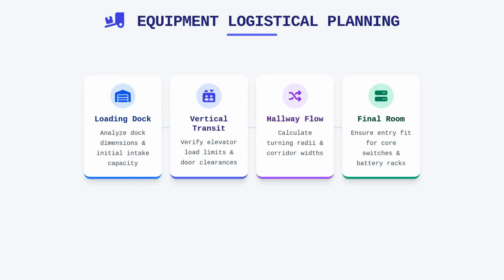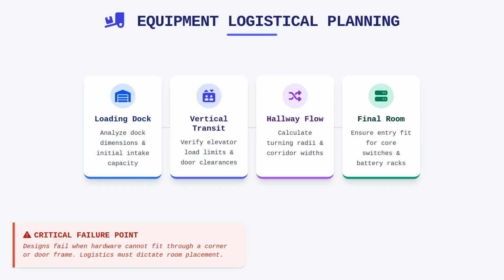It is an unfortunate but common reality that an impressive design fails in the field because a piece of hardware simply cannot fit through a corner or a door frame. Rigging requirements for oversized equipment must be part of your early planning, as these logistical constraints often dictate where an equipment room should be placed in relation to the primary building entrance. If the hardware cannot reach its destination without being disassembled, you have failed to account for a fundamental physical constraint of the facility.